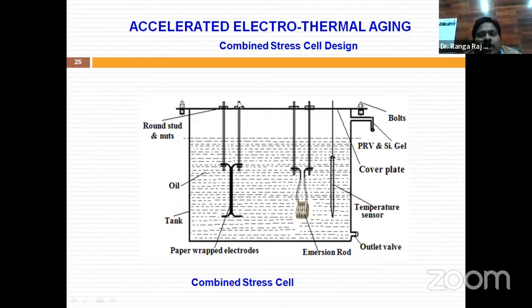These two electrodes are subjected to a high voltage transformer, as I discussed in the solid dielectric test, so with that setup we can apply the high voltage test. The two copper electrodes are insulated with this solid insulating paper material. Whatever stress we apply to these electrodes is applied to this insulating paper material, and it definitely loses its properties with respect to electrical stress. Similarly, the paper and oil lose their proper performance with respect to temperature rise.